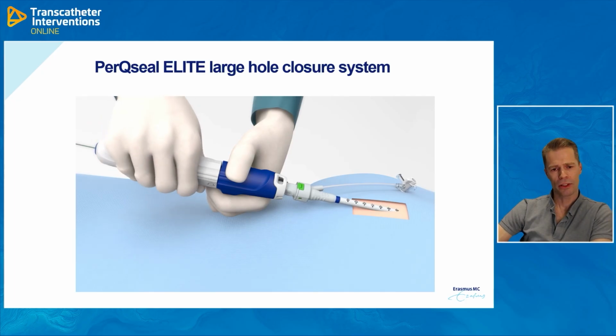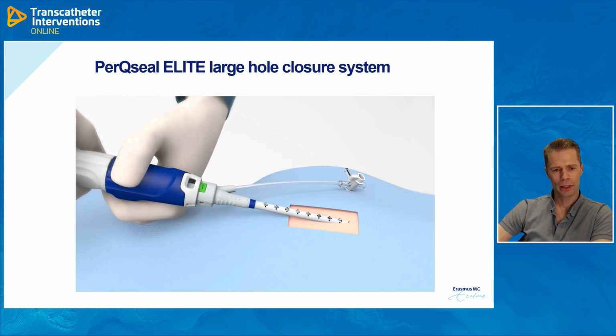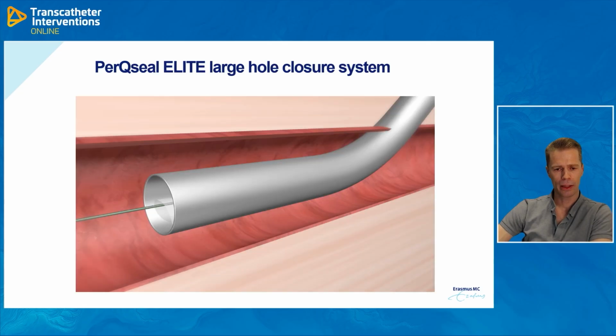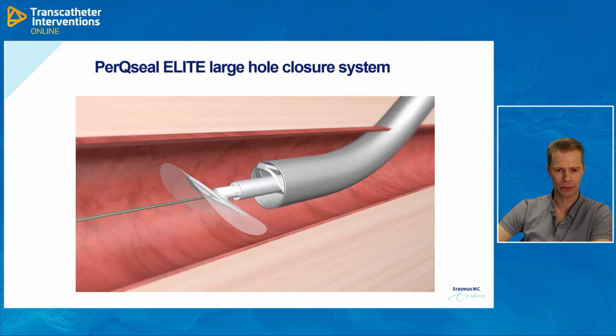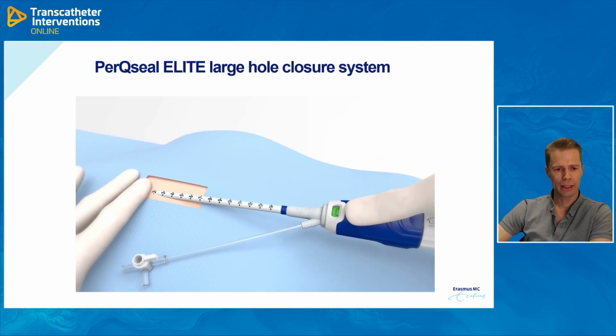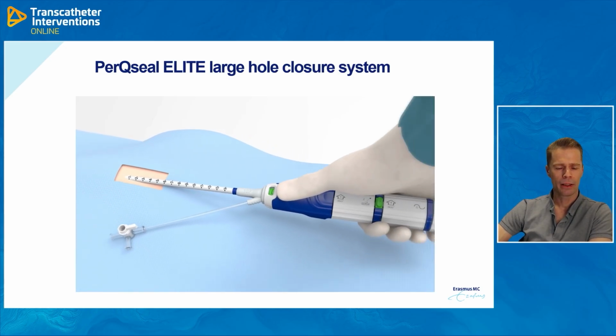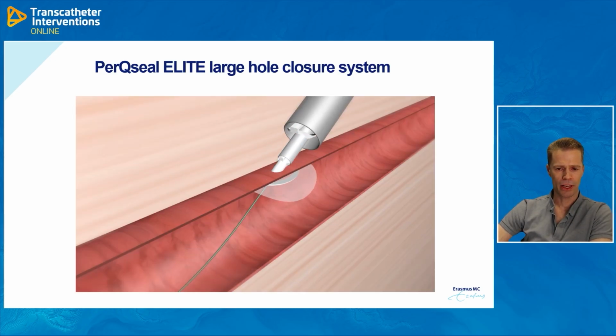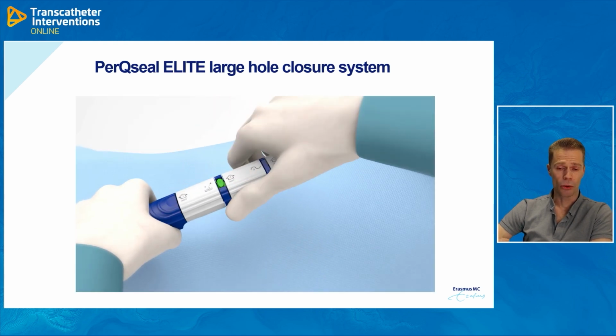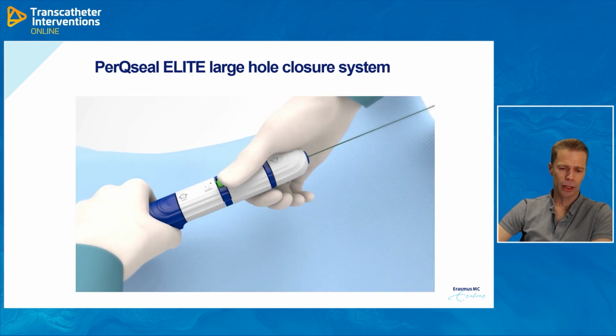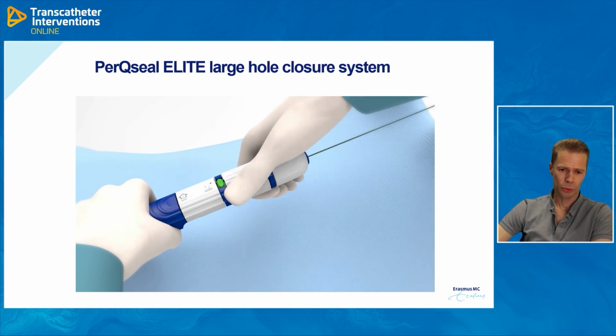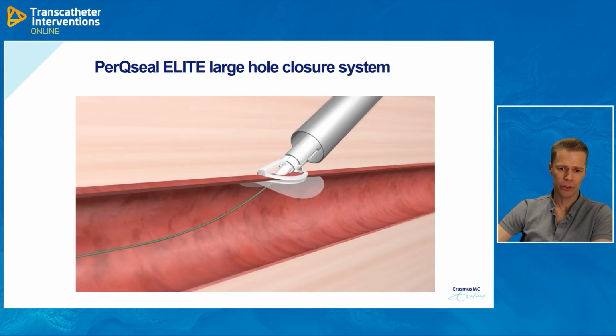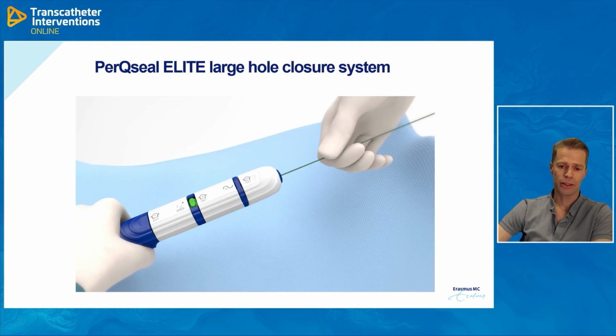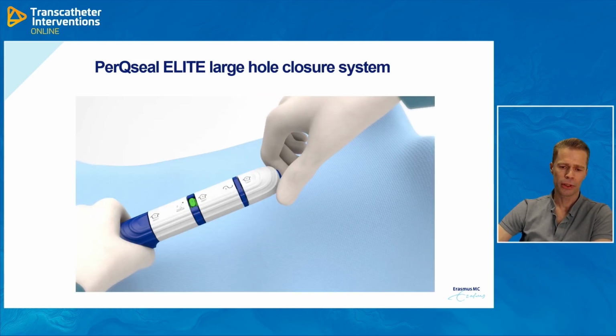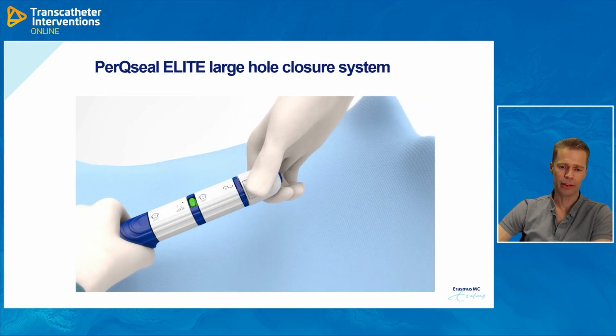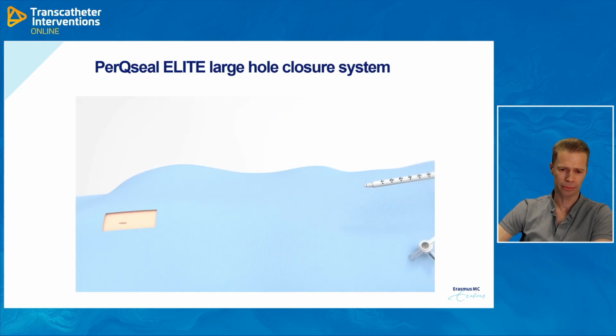The first step is to clockwise rotate the first knob, and this will essentially pull back the sheath. This results in the release of the patch in the blood vessel. Then you pull on the system gently, and this is where the tactile feedback comes into play, where the patch really is apposed to the blood vessel. And this will be the moment where you see no residual bleeding. The next step is to clockwise rotate the second knob, and this will result in the appearance of a second component that sits on the outside of the vessel. And then the last step is to remove the wire and release the delivery system from the device itself.